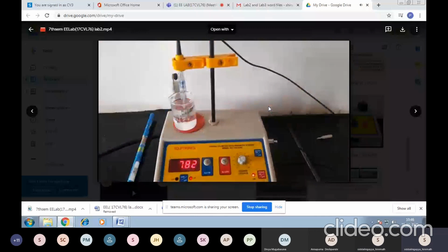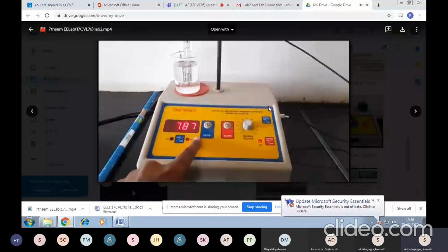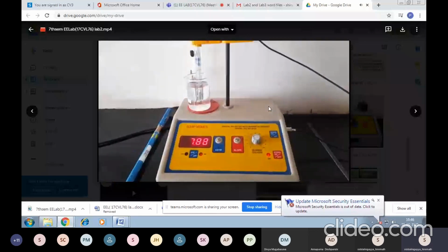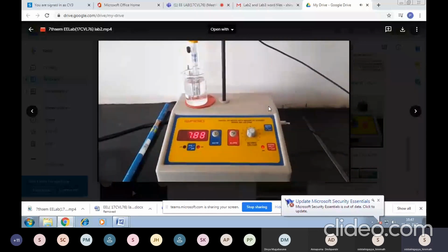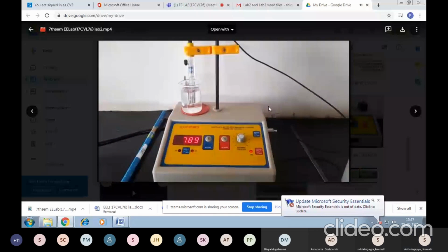Asymmetry potential. This is to nullify the asymmetry potential of the electrode. In general, asymmetric potential remains fairly constant for a period of a few weeks for a given pair of electrodes. Thus, once set, it may need adjustment once in 3 months.